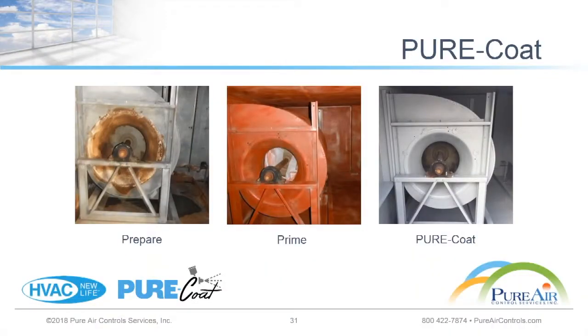Excellent, so that's the pure steam process. Once we get done steaming the inside of the air handler unit, bringing that efficiency back to the coils, everything is clean and ready for any additional preparation, and then we're ready to start doing the coatings. If there's a rust issue within the unit, you're obviously going to remove that rust through a variety of different ways. One way we use is a garnet blasting method. Once all that rust is removed and we've identified and made sure all the components are working correctly, we'll go in there and prime and coat the unit.